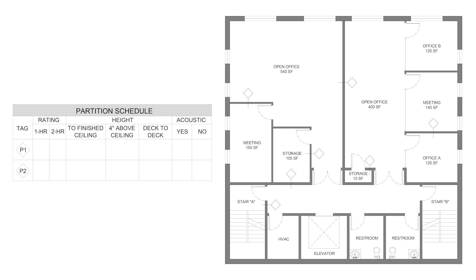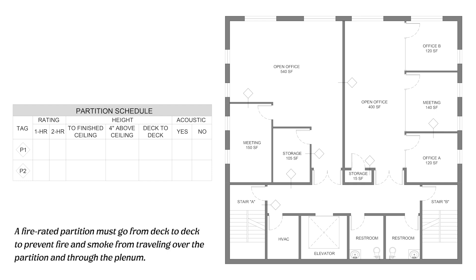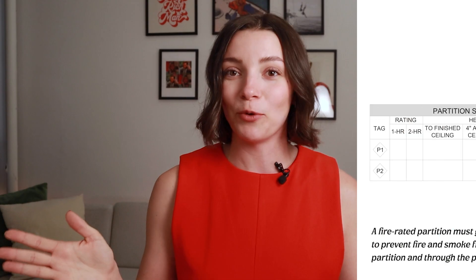For the purposes of this example, I want to quickly note that a fire rated partition always goes to the deck. If a partition only stops at the finished ceiling, there is that plenum space above — between the ceiling and the deck — that fire and smoke can travel through, and that wouldn't be a fire rated partition. So as a note, all fire rated partitions must go all the way to the deck.